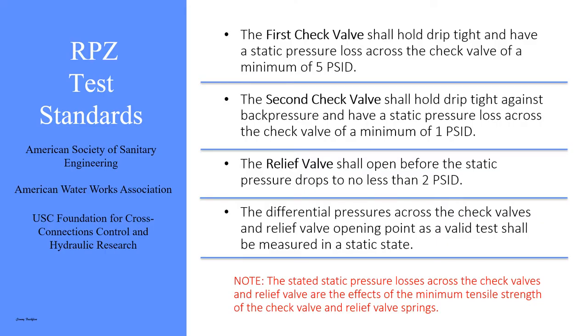RPZ test standards. The reduced pressure principal backflow prevention device assembly shall meet certain standards: the first check valve shall hold drip tight and have a static pressure loss across the check valve of a minimum of 5 PSID. The second check valve shall hold drip tight as well against back pressure and have a static pressure loss of a minimum of 1 PSID.